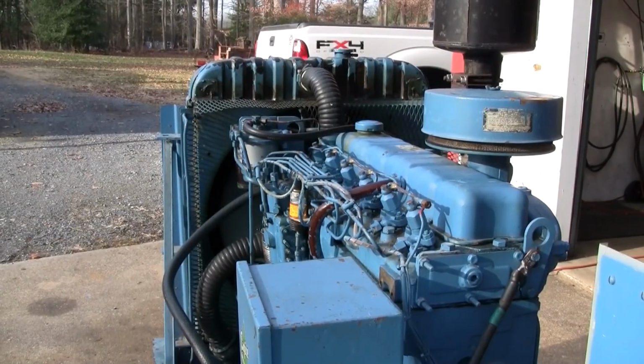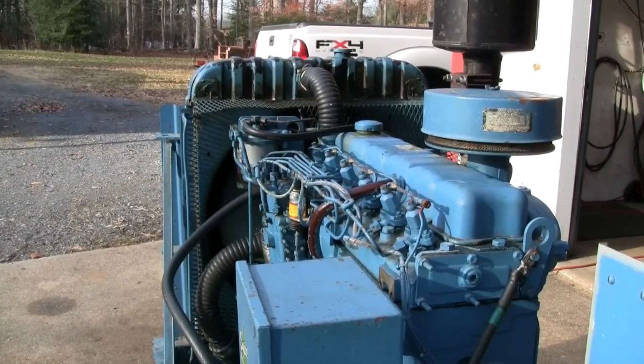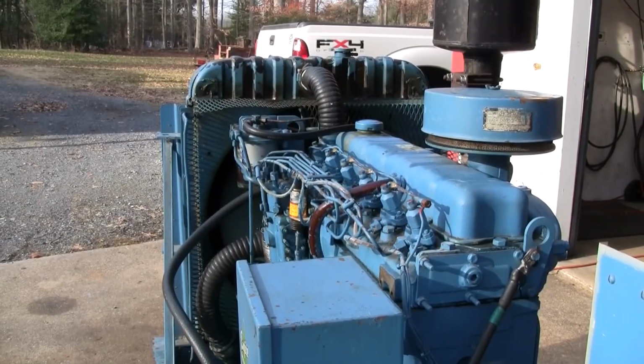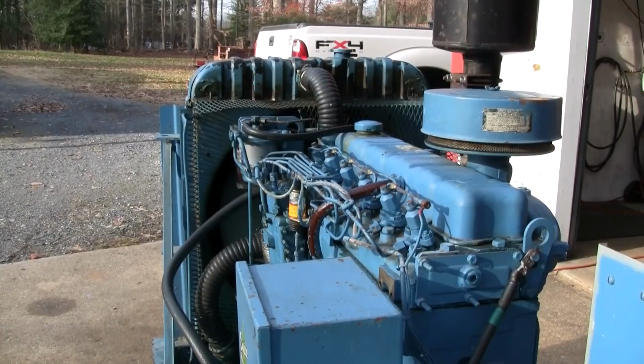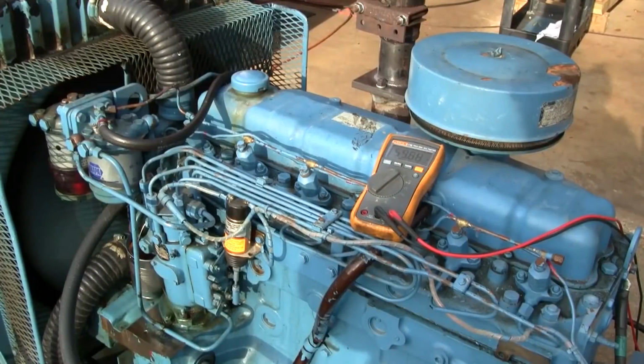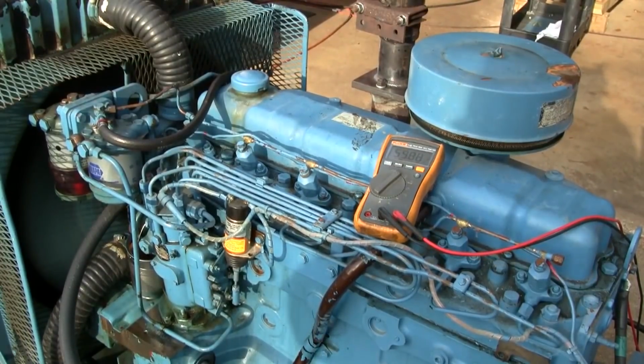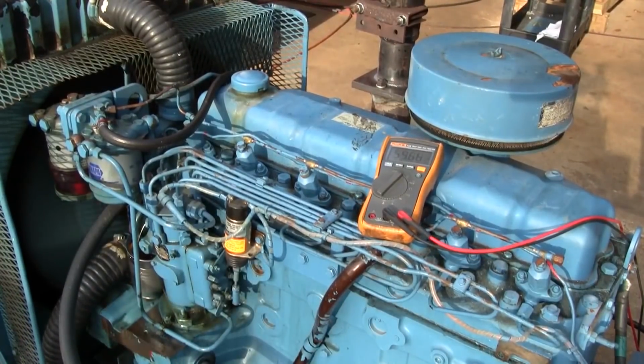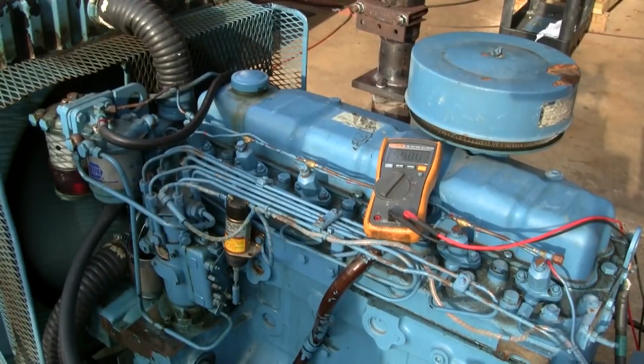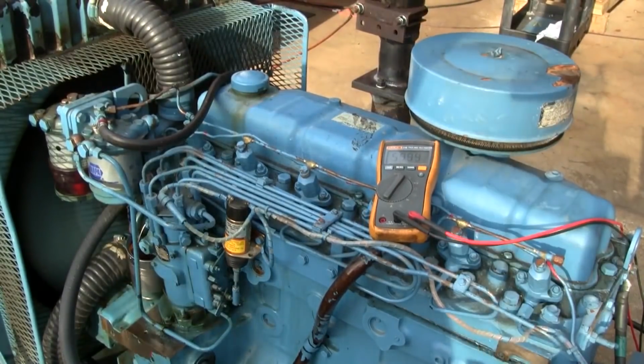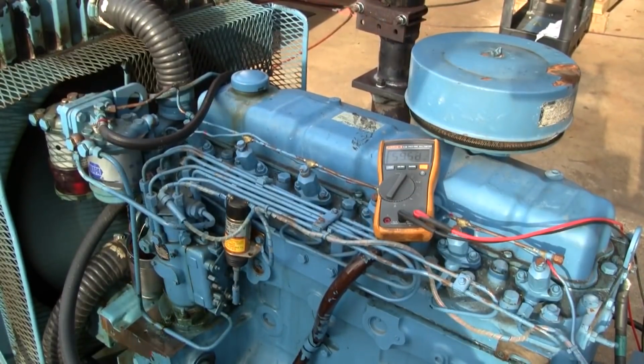Down to 22 kilowatts. I think I'm going to need a 1/4 inch wrench so that I can turn the fuel up on the injection pump when we're under heavy load, just to see if the engine has the horsepower to maintain 60 hertz at that load. We'll be back in a sec. It's actually a 5/16 wrench I need. So we are still at 22 kilowatts. I don't know if you can read that meter, but we are at 59.5 hertz.